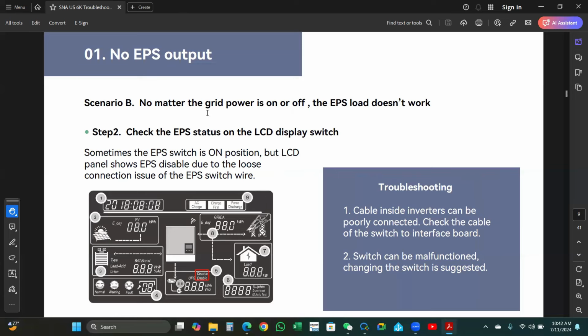Scenario B, same thing. No matter whether the grid power is on or off, the EPS load does not work. Step two, check the EPS status on the LCD display. Sometimes the EPS switch is on, but the LCD panel shows EPS disabled due to a loose connection issue of the EPS switch wire. Troubleshooting, number one, the cable inside the inverter can be poorly connected. Check the cable of the switch to the interface board. The switch can malfunction; changing the switch is suggested. For diagnosing, you can bypass the switch. This is where you see on the LCD, disable or enable.